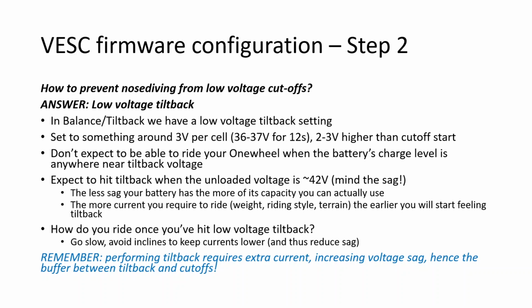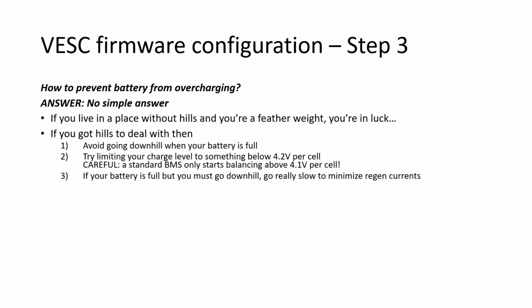Also, you've got to remember that performing the actual tilt back requires extra current, which increases voltage sag. That's why you need a buffer between the tilt back and the cutoffs. You don't want to set your tilt back to just 1 volt above the cutoff. Otherwise, the act of performing tilt back will take you right into the cutoff zone, and then you've got a cutoff with tilt back. That's not what we wanted to achieve.